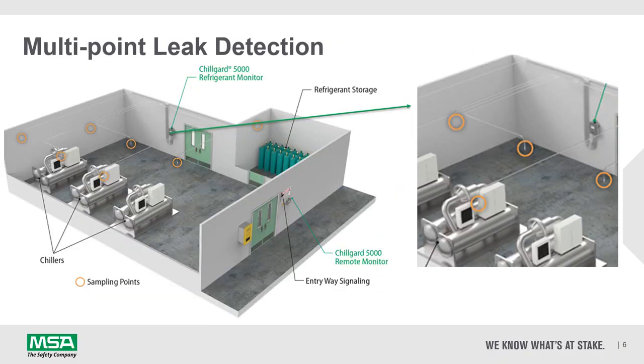Here is an example of a chiller plant room using a multi-point leak detection system. As you can see, the room has a number of chillers and a refrigerant storage area. Sample points, ceiling mounted, are individually tubed back to the refrigerant monitor located on the left-hand side of the door inside the room. From the refrigerant monitor, audible and visual alarms can be activated to ensure that personnel are warned and can evacuate the area. An additional connection can be made to a remote monitor positioned outside the room, which can also be used to initiate audio and visual alarms to prevent people from entering in the event of a refrigerant gas leak.